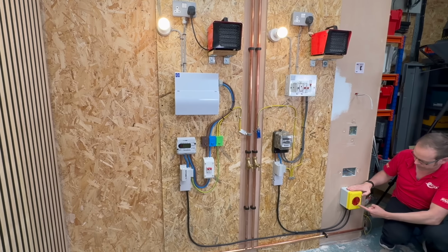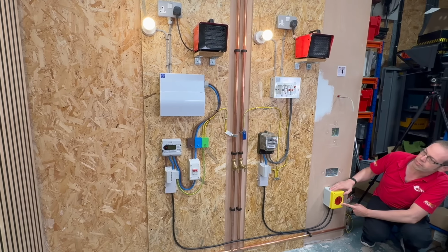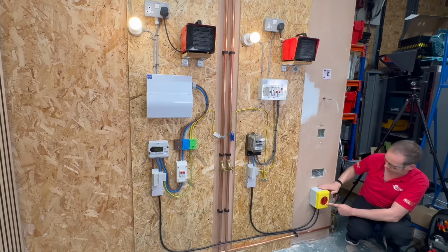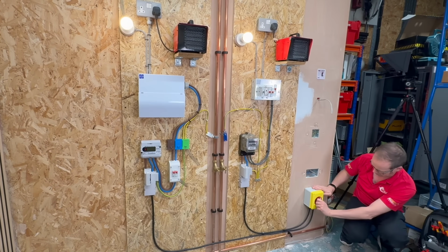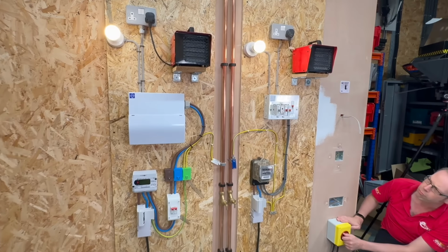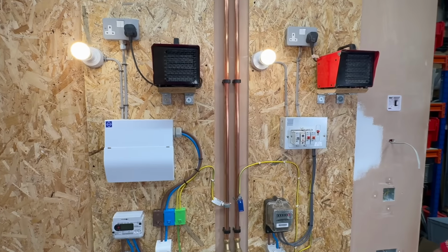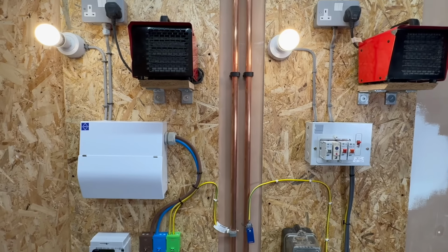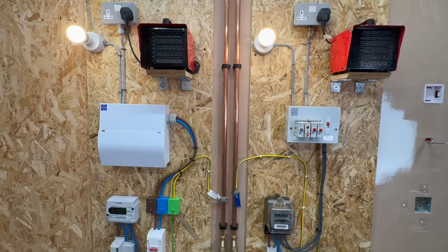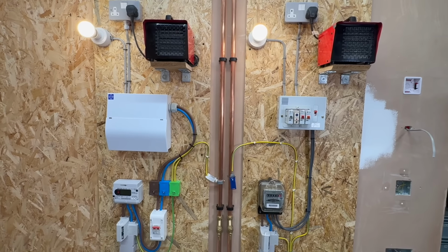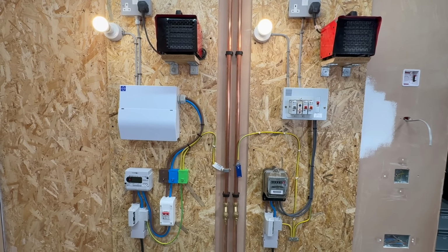I'm going to operate this switch down here, and it will disconnect the combined neutral and earth connection to this simulated property. Okay, hold on to your hats. Here we go, and... yeah. Well, that was anticlimactic, wasn't it? I've just introduced a potentially life-threatening fault into this system, and nothing's tripped. Everything's working as it was before. There's not even a flicker of a light or anything else to indicate that there's a huge problem here.